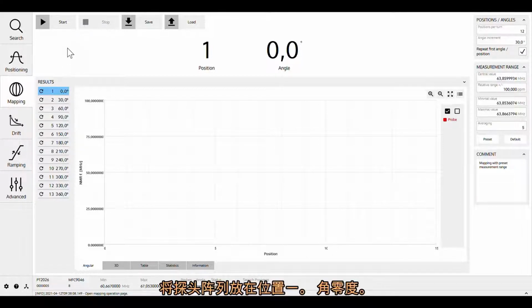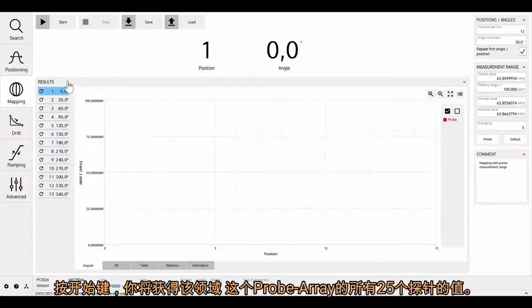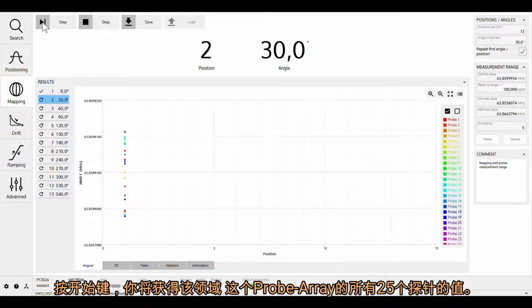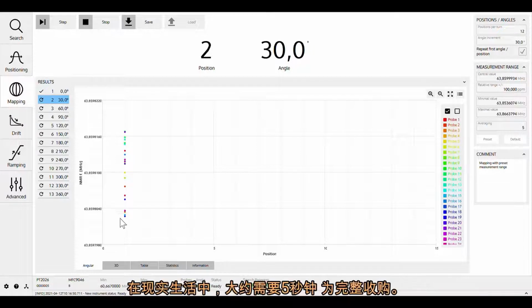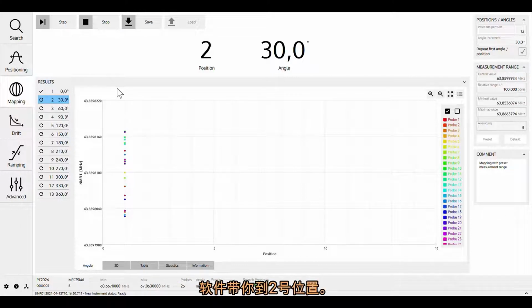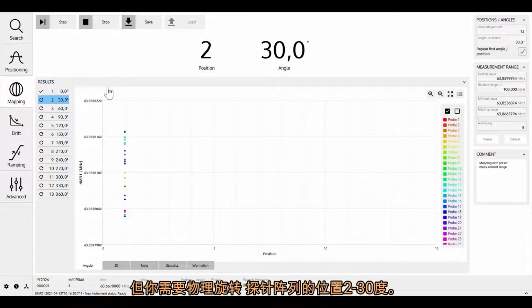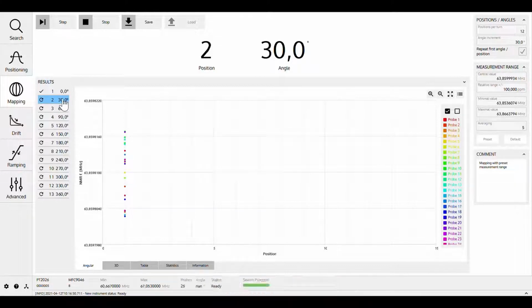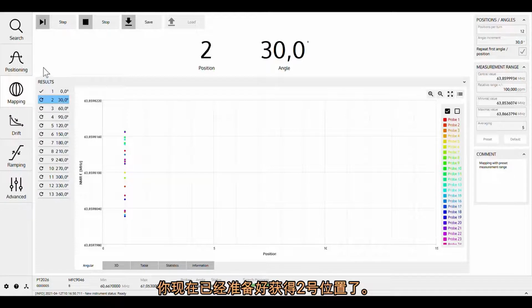Place the probe array in position 1, angle 0 degree. Press Start and you acquire the field value for all 25 probes of this probe array. In real life, it takes around 5 seconds for the complete acquisition. The software takes you to the position 2, but you need to physically rotate the probe array to position 2, 30 degrees. You are now ready to acquire position 2.